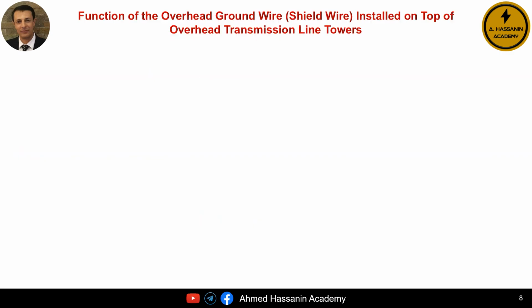We have generally understood together the importance of earth conductors or shield wires, whether of the traditional type or the optical ground wire, OPGW type. However, we want to understand in more detailed terms the importance and function of the earth conductor or shield wire located at the top of the overhead transmission line towers.